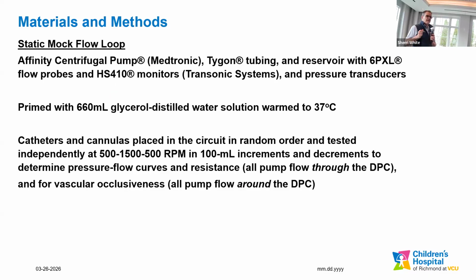So the catheters and the cannulas were placed in the circuit in random order and then tested independently at speeds of 500, 1,500, and back down to 500 RPM in 100 mL increments and decrements. So they generated 2 data sets for each of the catheters and cannulas.